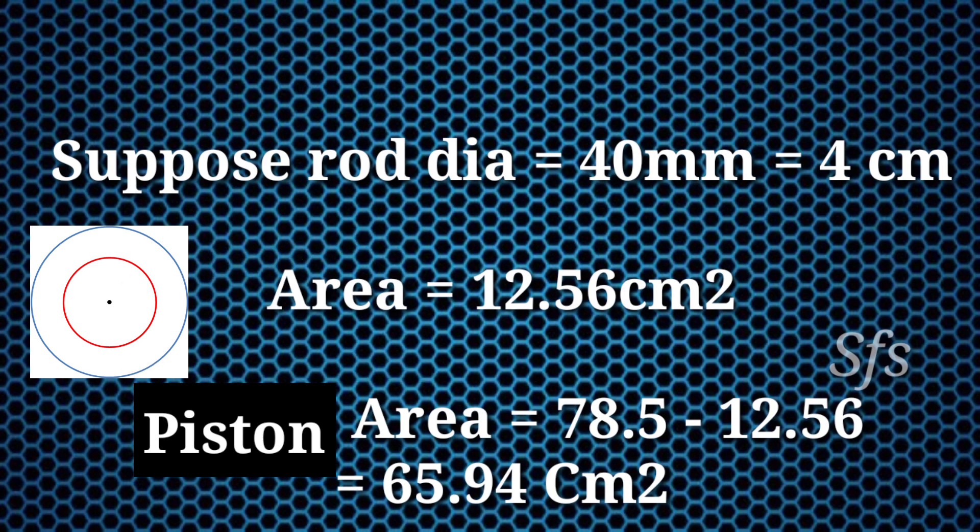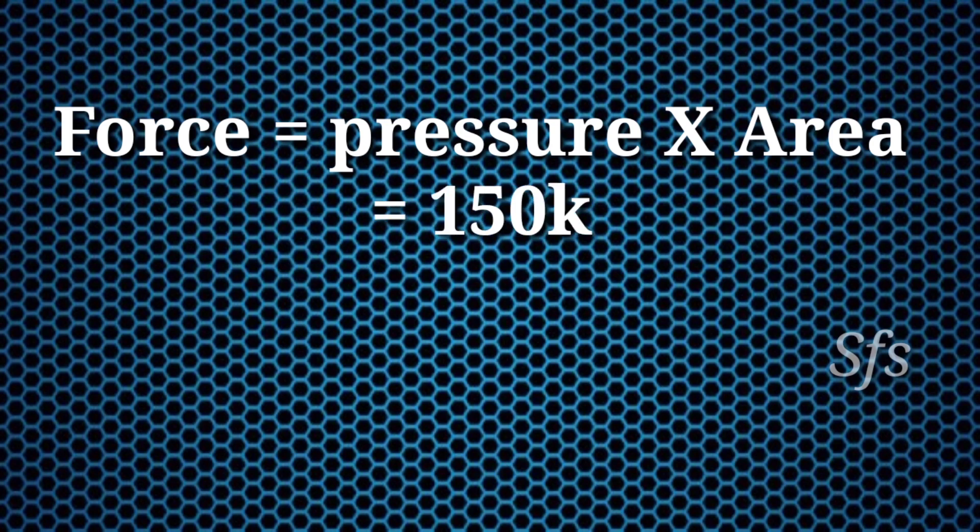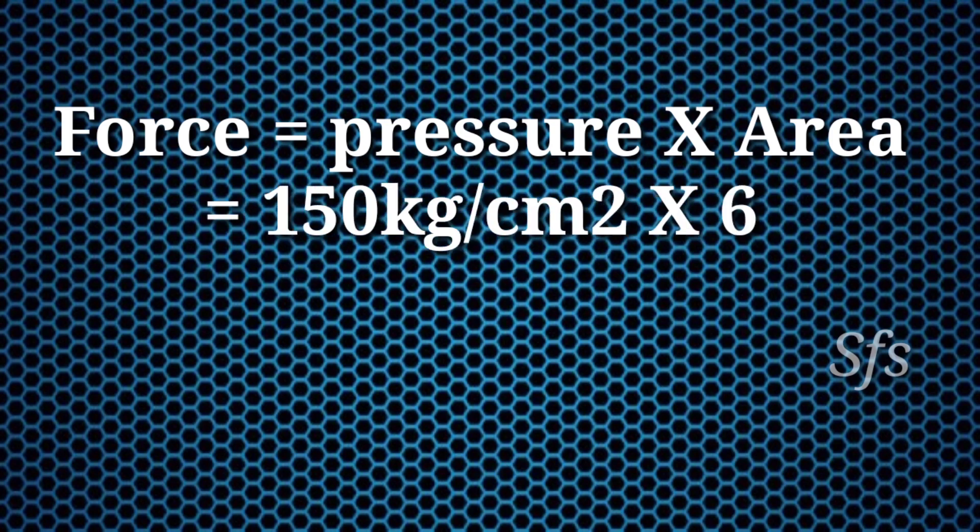The total piston area is 78.5 cm squared. The area of the rod is 12.56 cm squared, calculated with formula π r squared. We subtract the rod area from piston area: 78.5 minus 12.56 equals 65.94 cm squared.